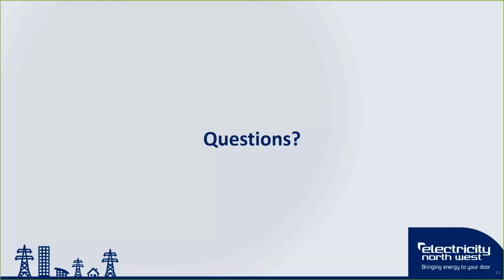The second question has come through, similar to what I've just said actually. If the EV charger is being connected to an existing supply, does the supply require a maximum import capacity increase? Again, this is determined by the customer. Some customers install chargers and charge vehicles throughout the night, company vehicles being charged through the night, where the maximum demand is quite low and it's not impacting on the maximum import capacity.